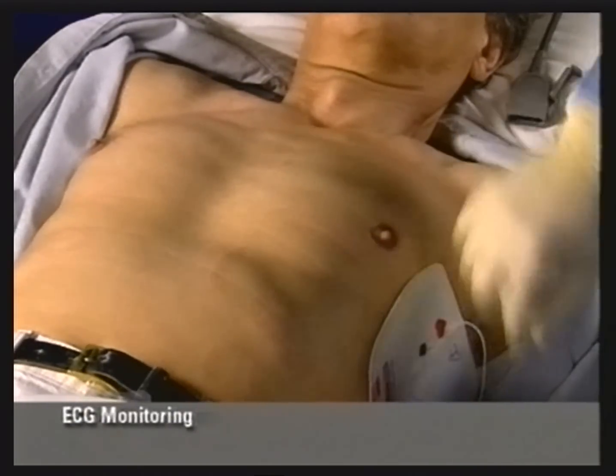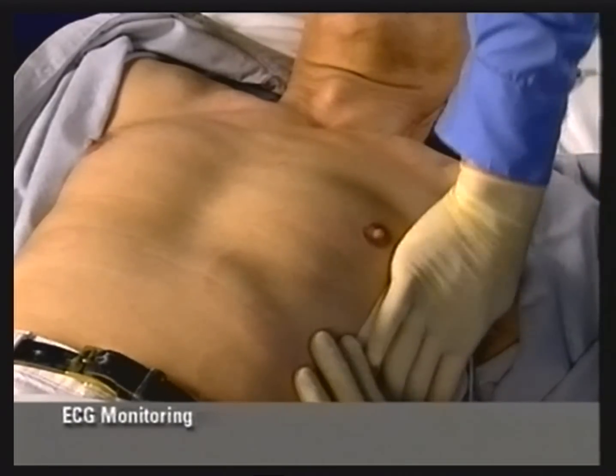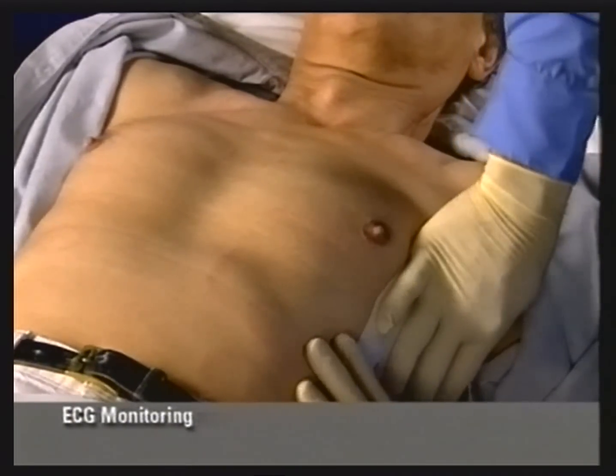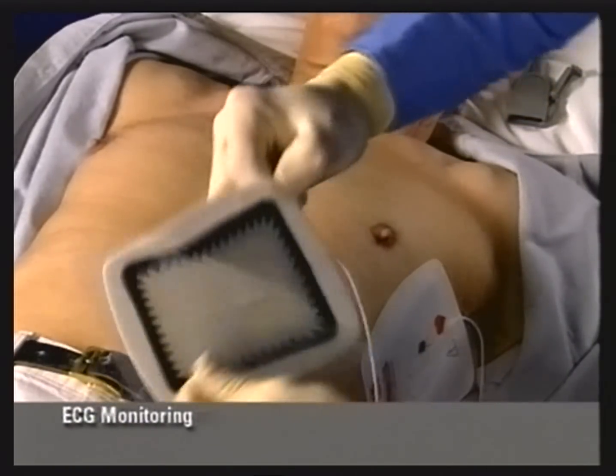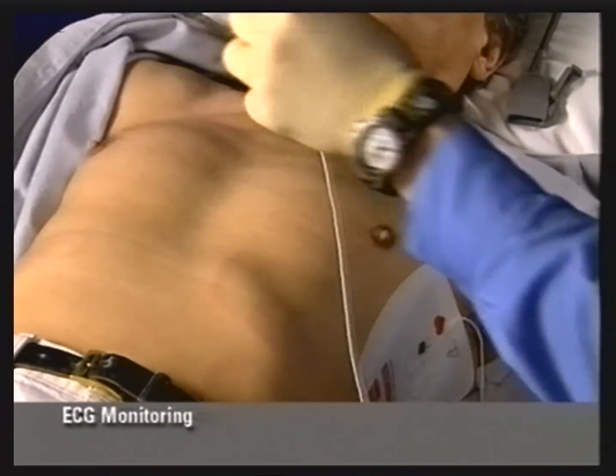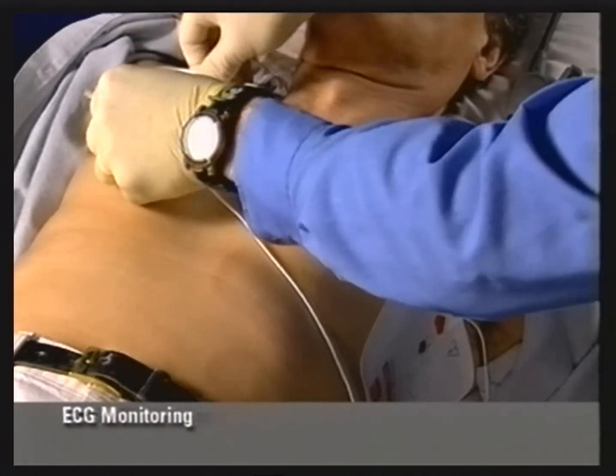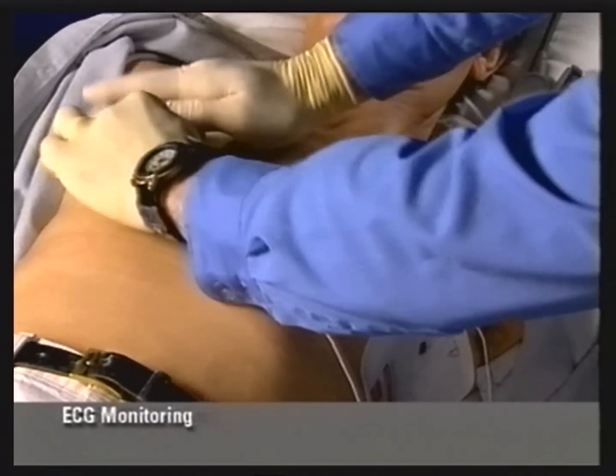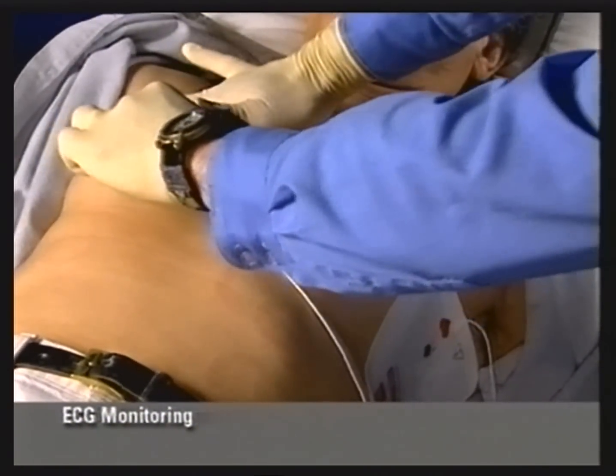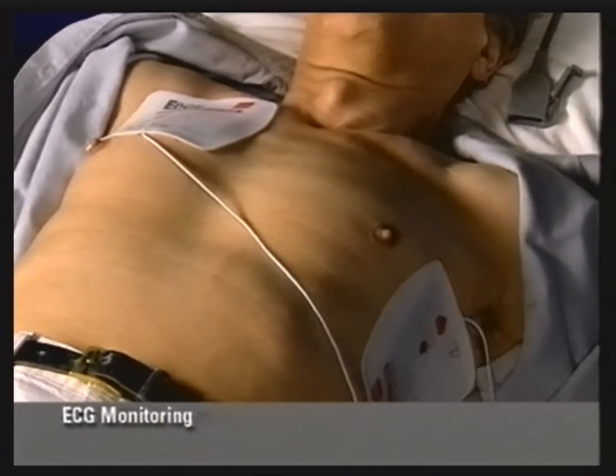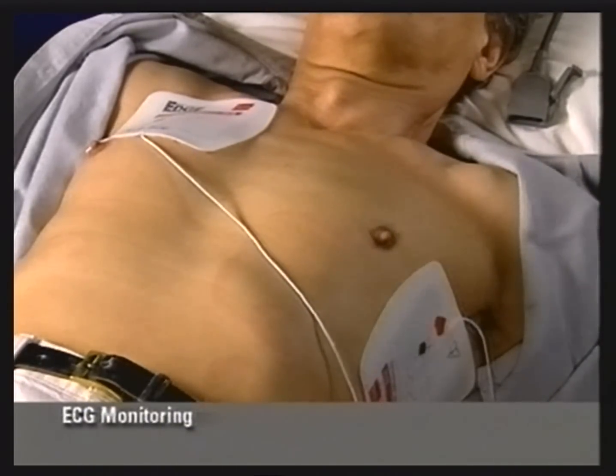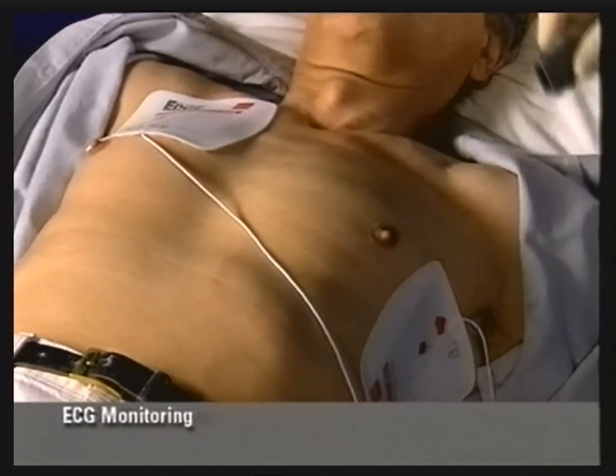The electrode with heart symbol is placed lateral to the patient's left nipple in the mid-axillary line. The other electrode is placed to the right of the sternum below the clavicle. Press the electrodes firmly from one end to another to prevent entrapment of air. Connect the electrodes to the therapy cable.